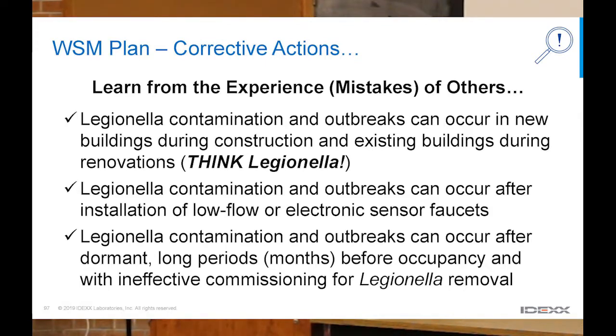We've mentioned low flow. That should be a key, because I told you it's very important to stay out of the bad temperature range, have a good disinfectant range, have good flow, no stagnation, no dead legs, not let biofilm grow, and not have bacteria, Legionella, growing. So we just learned these systems have been associated with disease contraction after installation.